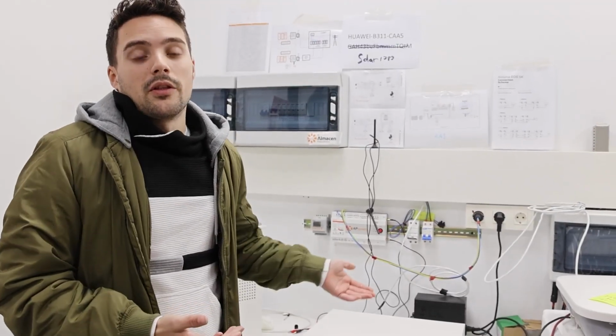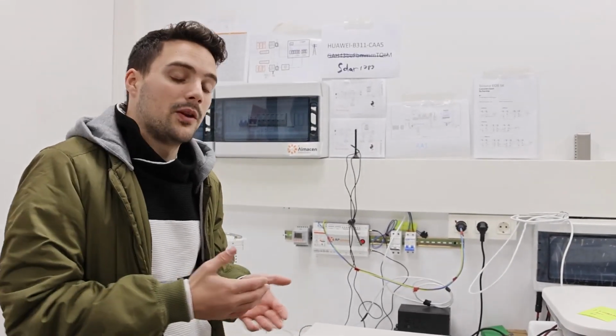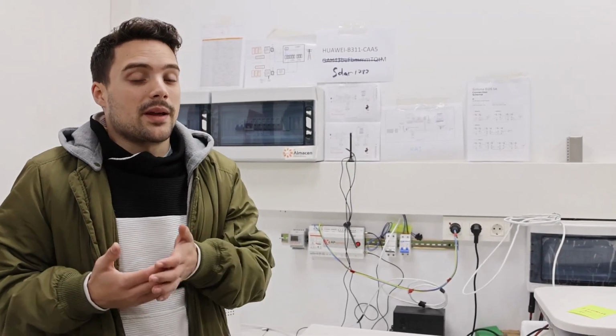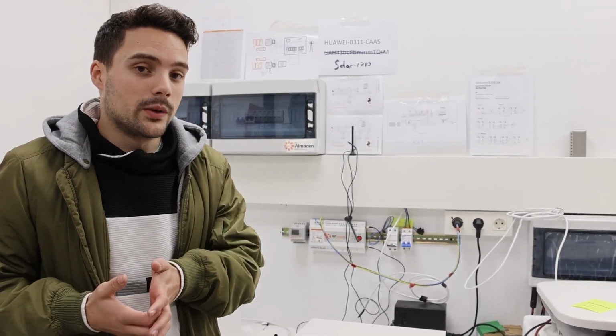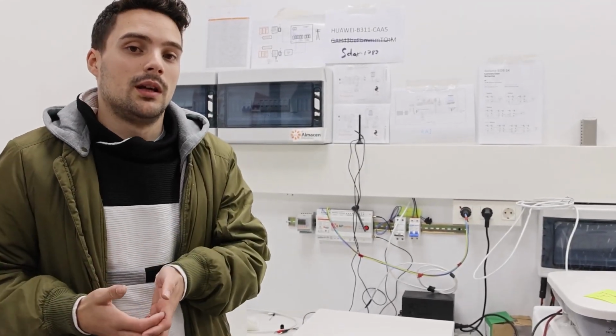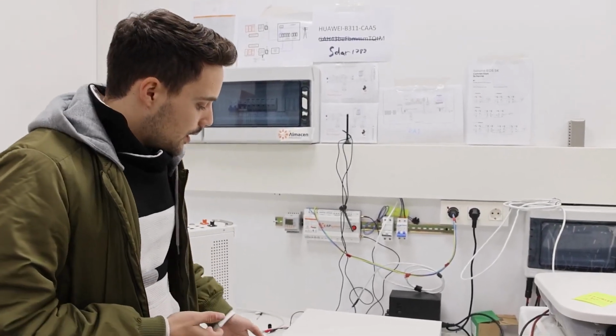So if there were 5 batteries in the bank and 2 of them have less voltage, even though we've repaired the ones where the short circuit occurred and they are providing the correct voltage, these slightly damaged ones do not allow reaching the minimum voltage at which the battery management system turns on and can work. Therefore, the fuse in this one must also be changed.